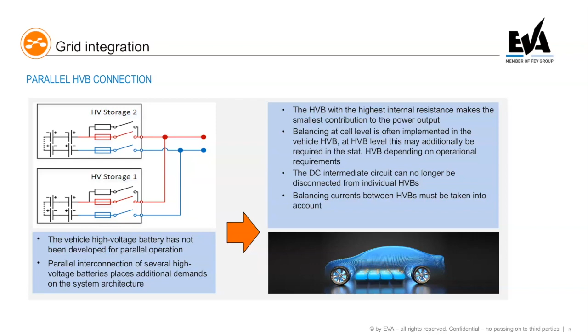Then balancing is also interesting. Normally when you drive an electric car, you drive 1 hour per day. A stationary plant operates 24 hours. So balancing at cell level is often implemented in the vehicle, and at high voltage battery level, this may additionally be required in the stationary battery, depending on operational requirements. And the DC intermediate circuit can no longer be disconnected from these individual batteries, and the balancing currents must be taken into account. It's very important.